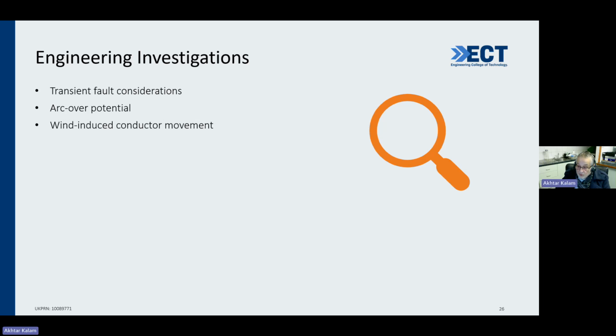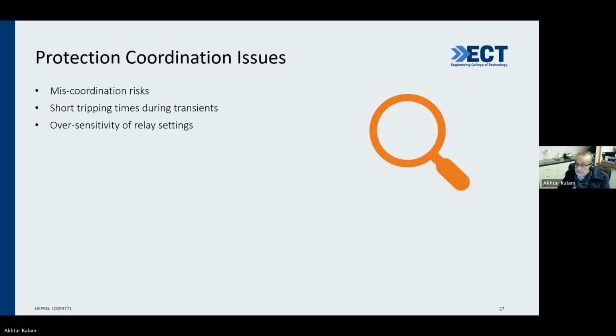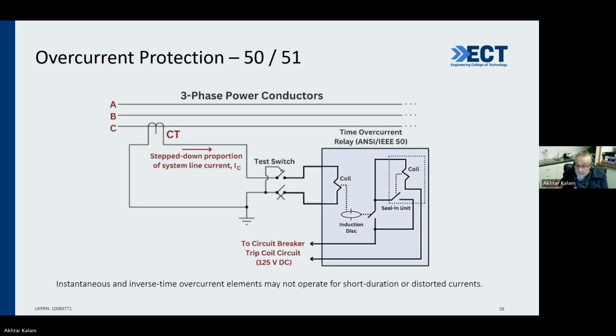Now, after that, I want to look at the coordination of the protection. Definitely, there is a risk of miscoordination. Definitely, there is a transient period of very short duration. And definitely, the relay sensitivity is there. These things are oversensitive to the relay settings. So, my friends, I now look at my protection. It is a typical inverse time overcurrent element. That means current is inversely proportional to time, so if the time increases, the current decreases. And this is a device called 50/51 for overcurrent protection.